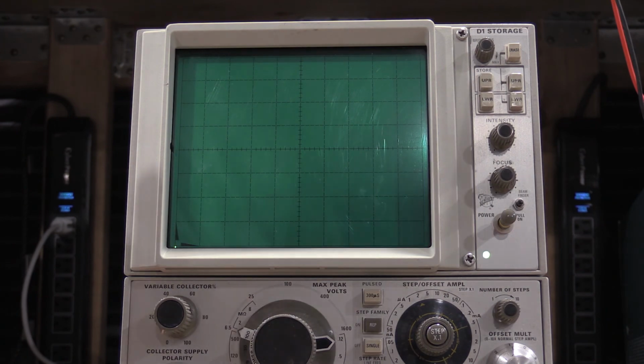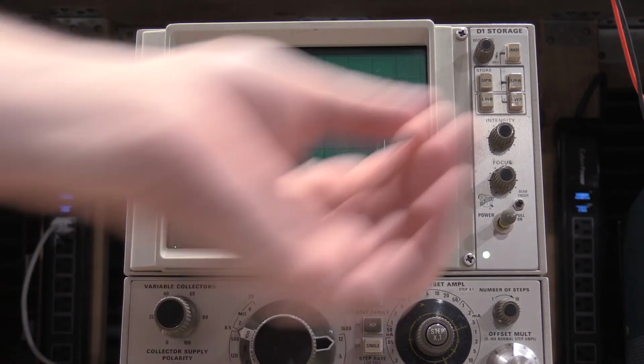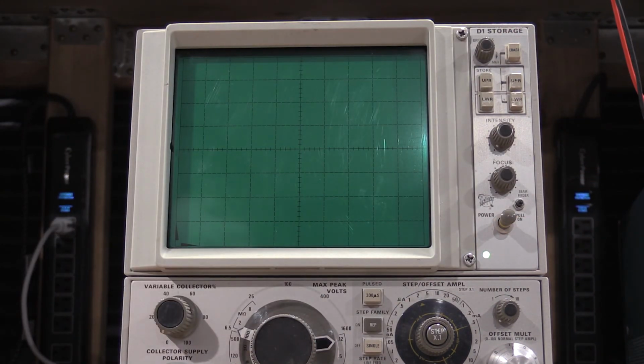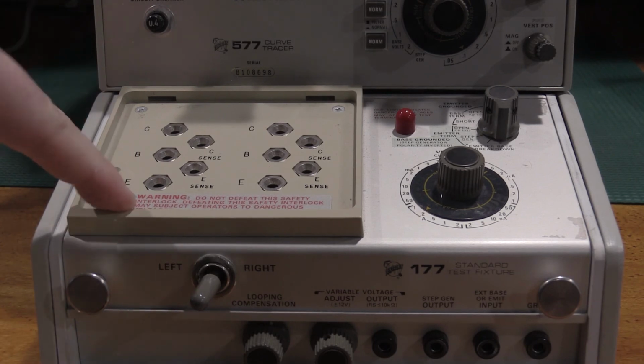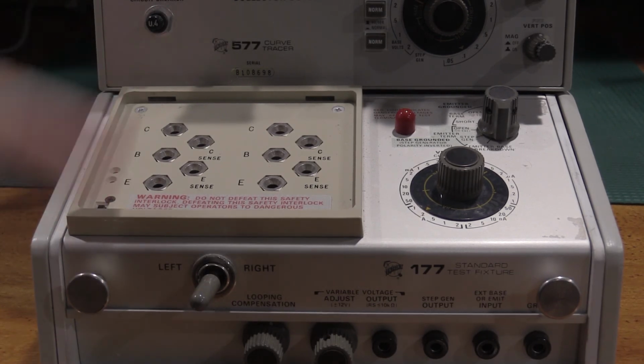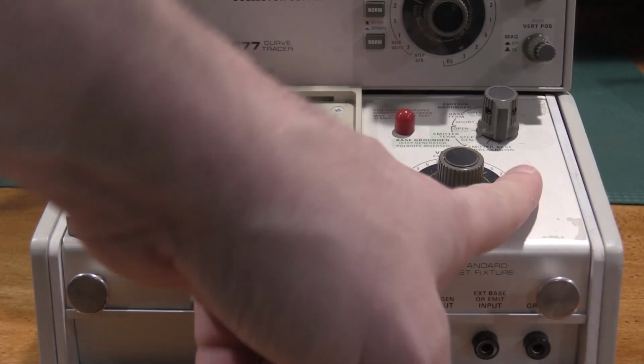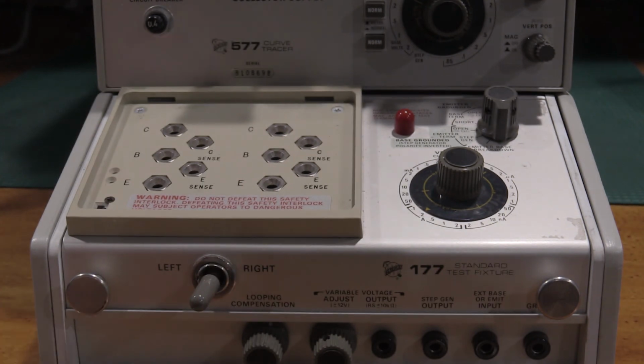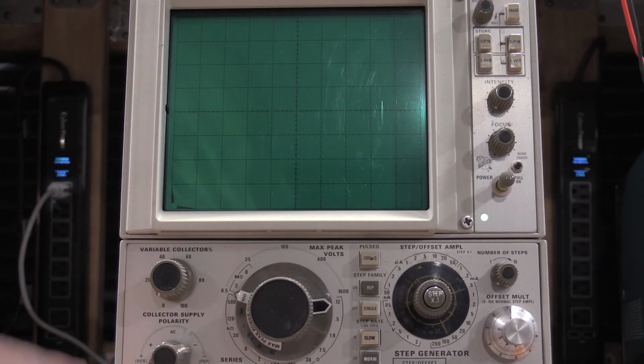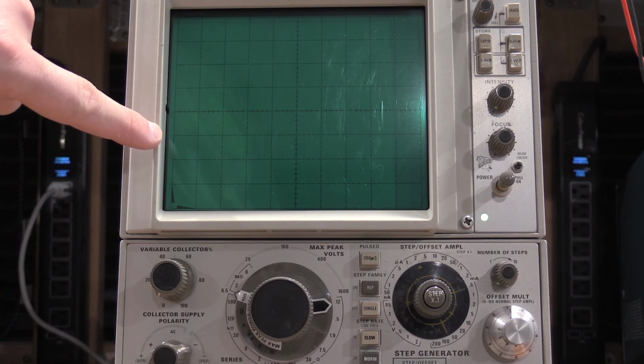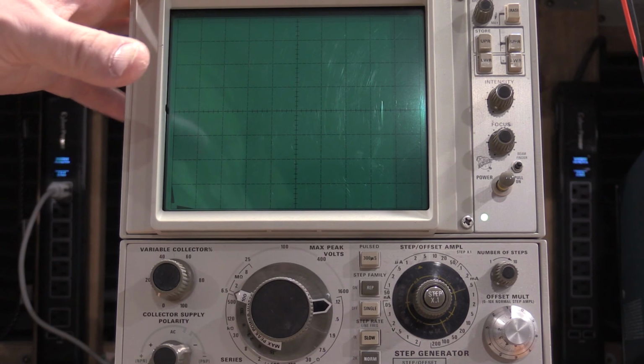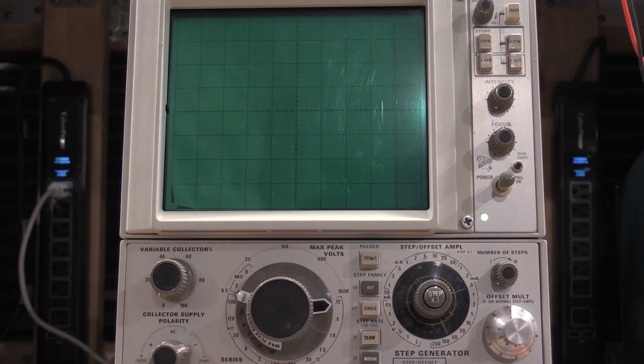I ran into that problem, and this was the rabbit hole that I dove down on that older unit. I even thought the older unit was going bad, just well out of spec given the age. But what it turned out was there's op amps in the 177 that have to be adjusted first. If the 177 is not in spec, specifically the amplifier balance, that test that I did will never work right. On this unit, when I started before I did the 177, it was 3.5 divisions up. So it was up here. If you're going to work on these, one, if you're following along, you're doing so at your own risk. Two, make absolutely sure the 177 is done before you try to do the unit. Drove me nuts in the last one.